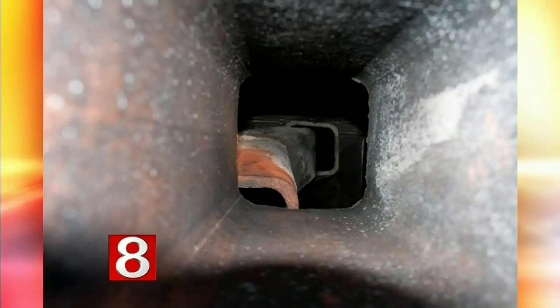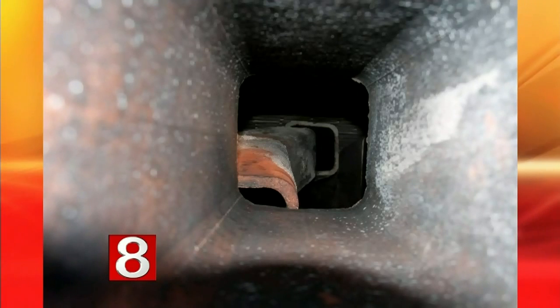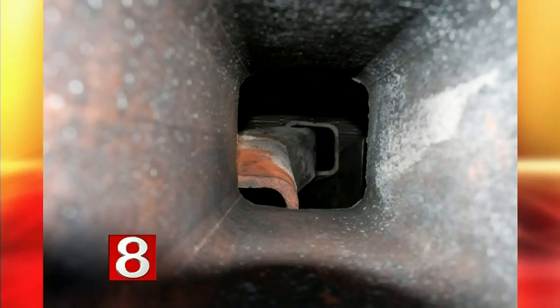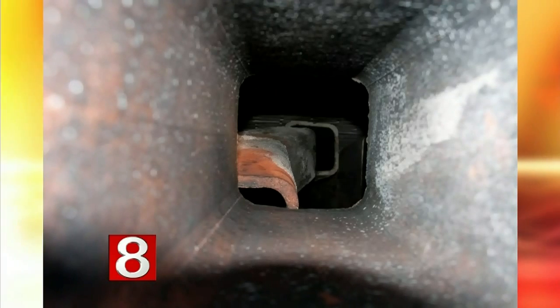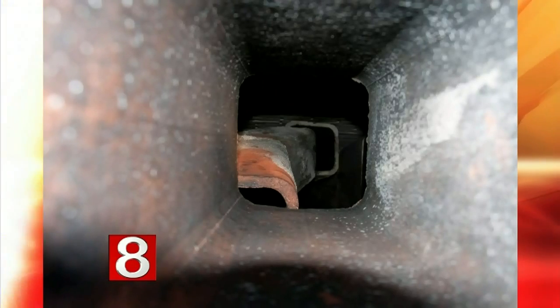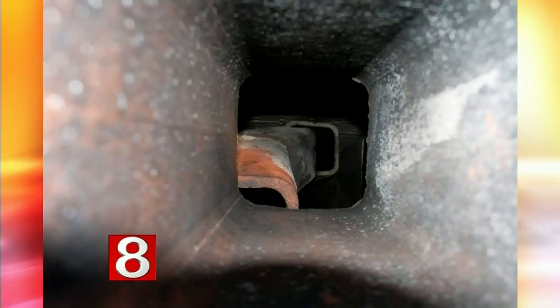Got it. Now, this is an example of... Oh, yes, that happens a lot. I look down a chimney and the tiles are staggered and there are gaps, allowing the gases and the soot to go basically wherever they want, flowing freely into your house. You don't want that at all. That's out of the question.